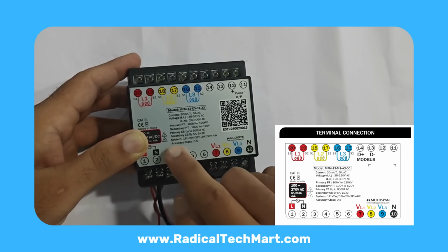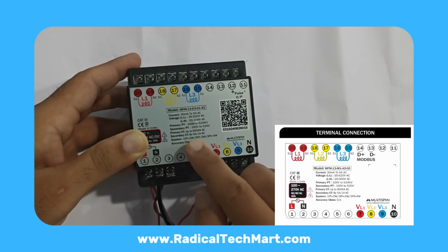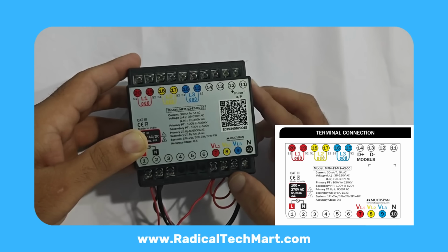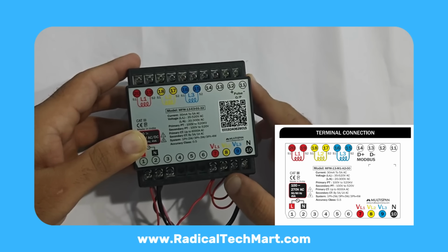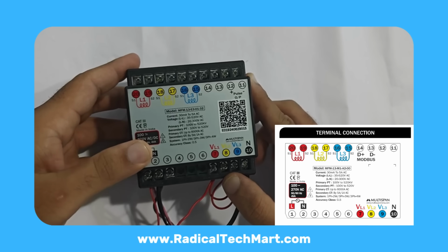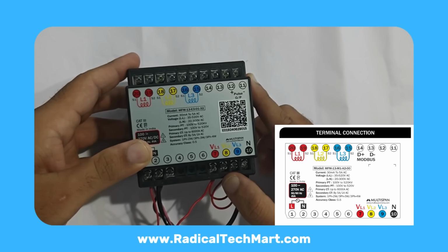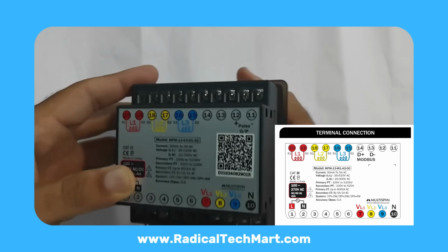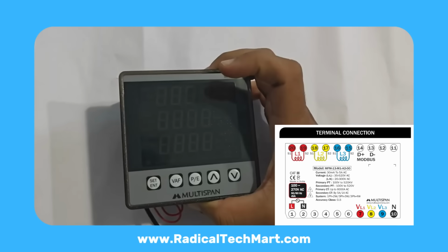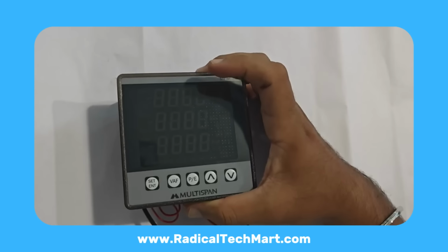CT, current transformer, ratios. CT primary, up to 6000 ampere. CT secondary, selectable between 5 amperes and 1 ampere inside the meter. So this meter can be used both in low voltage panels and in high voltage HT systems with PT and CT. Now let's power on the meter.